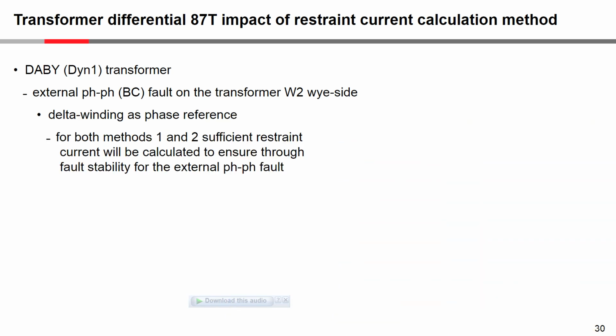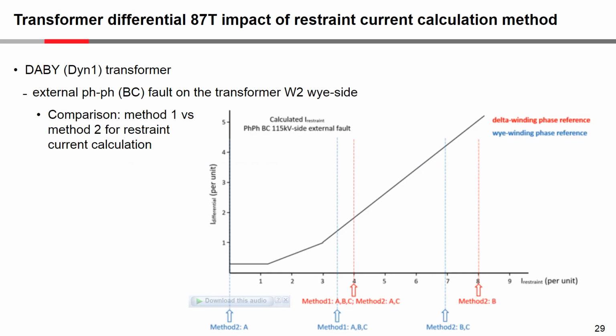So how does that impact us going forward? Well, for this BC fault, if we had the delta winding as the phase reference, remember the delta winding as the phase reference would give us the restraint current sitting at 4 per unit, and for method 2, phase B at 8 per unit.